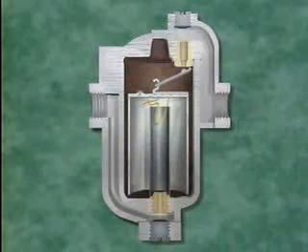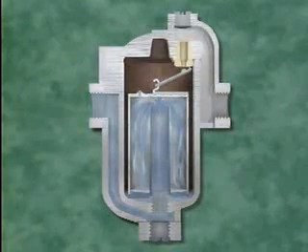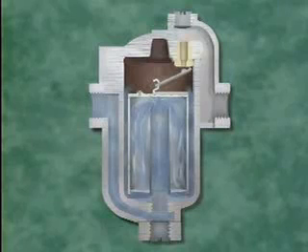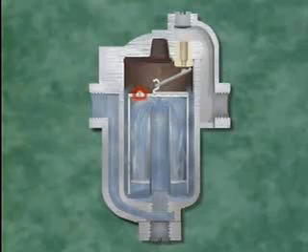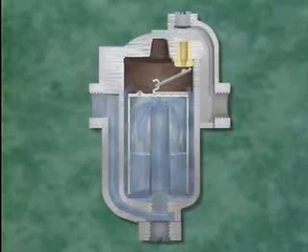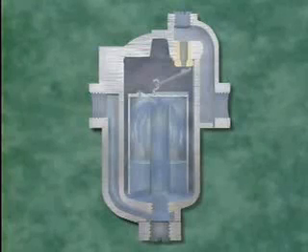During proper operation, the casing is filled with condensate to a level just above the top of the bucket, called the prime. The prime provides a water seal that prevents live steam from escaping the trap under the bucket. At startup, the bucket rests at the bottom of the casing and the trap valve is fully opened. Condensate from the steam system drains into the trap and flows under the bottom of the inverted bucket, passing between the outside of the bucket and the inside wall of the casing. As long as the trap is full of condensate, the bucket remains at the bottom and the trap valve stays open, allowing condensate to flow through the valve to the trap outlet.